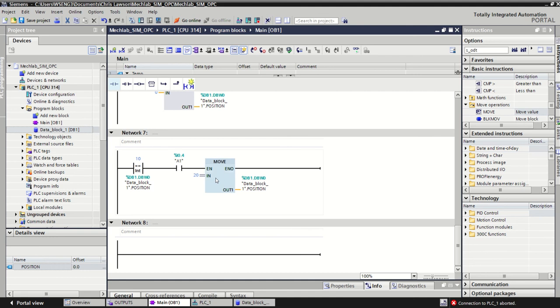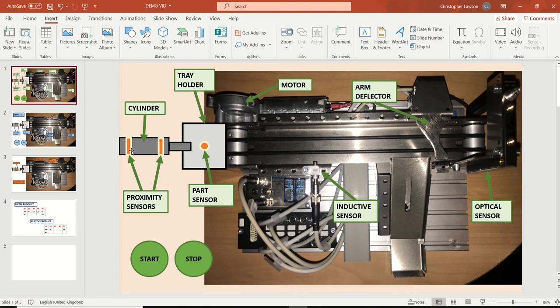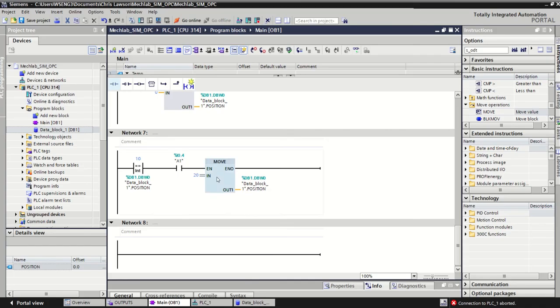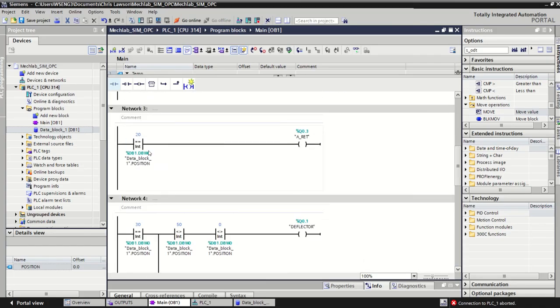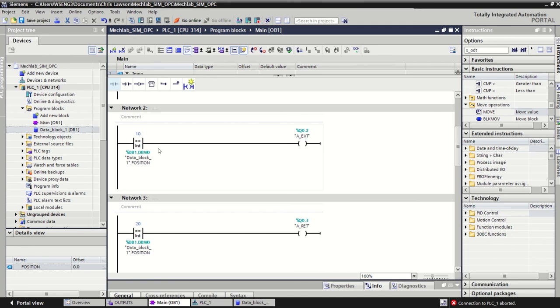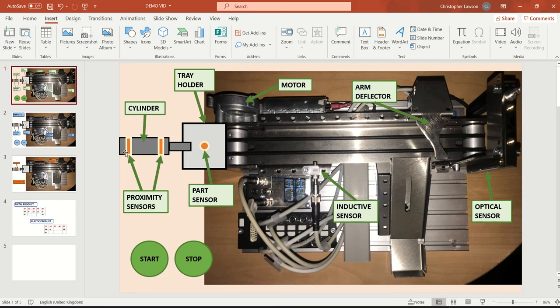Okay, so therefore it doesn't matter how long or how quick it takes for my cylinder to move forward, it won't go into the next step until it sees it's hit A1. So it doesn't matter, this is A1, this is A0, doesn't matter how long it takes for me to get there, as soon as it gets there, it will move to step 20, and then we know in step 20 A will retract because A is no longer extending because we're not in step 10 anymore. So that's the real benefit of this as well. You're not using any timing sequences or anything. So especially when you have two sensors there to tell you position, there's no reason to try and use a timer to see how long or how short that should come out. We want a full extension of the cylinder, and that's the way we do it.